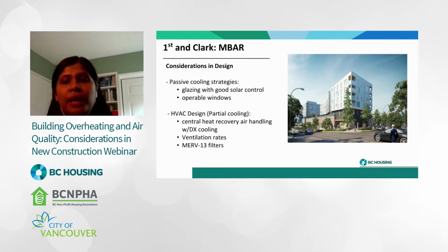For interior, though, for partly zone 5, 6, and 7A, it has full cooling inside residential units in our current design guidelines. The most practical and cost-effective way, while maintaining the affordability in the project in climate zone 4 and 5, is to have the partial cooling with higher ventilation rates through the central ventilation system in residential units. Also, this will address the outdoor air quality that Lisa was talking about during the wildfires. The level of filtration for the central HRV units by providing the MERV 13, and in addition, the space for future HEPA filter and also activated carbon filters.